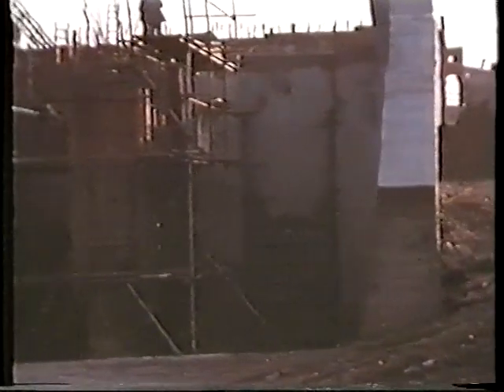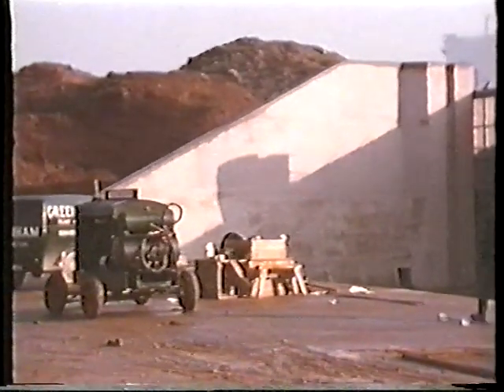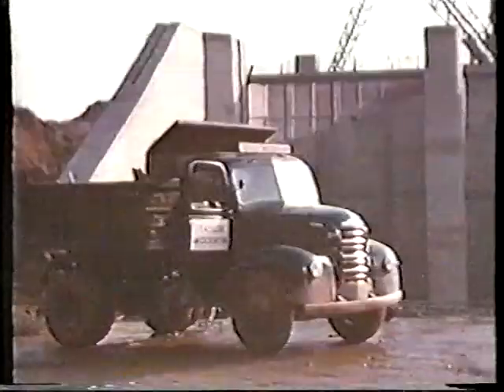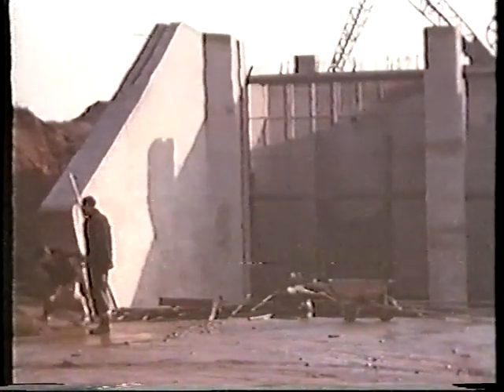These chambers are being constructed to house the 72-inch wide fine screens, which are of the mechanically driven band type. Penstocks will be installed in order that the chambers can be isolated for maintenance purposes. A penstock has now been placed in position, and the operating mechanism will follow in due course.